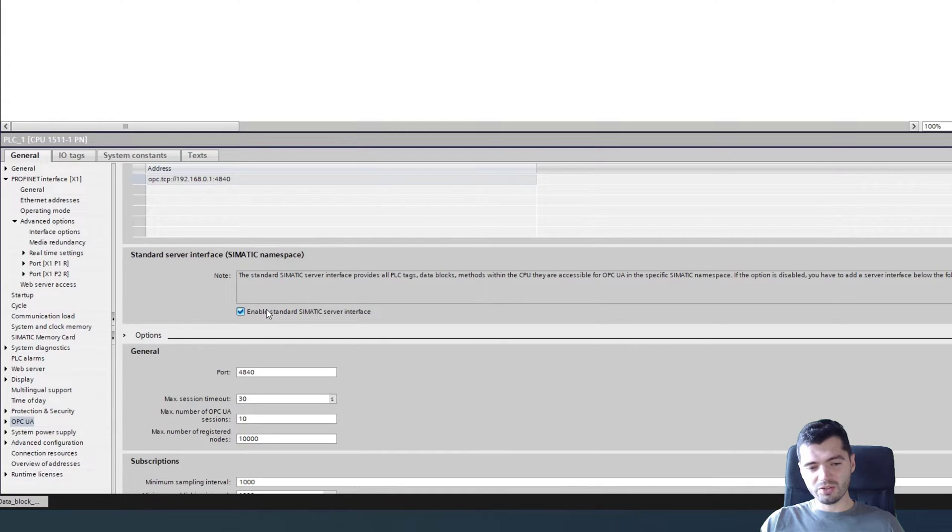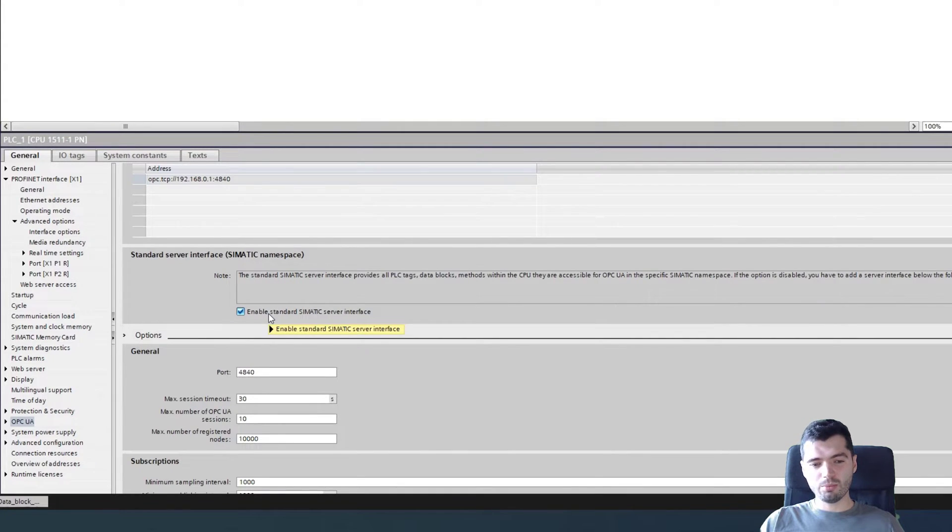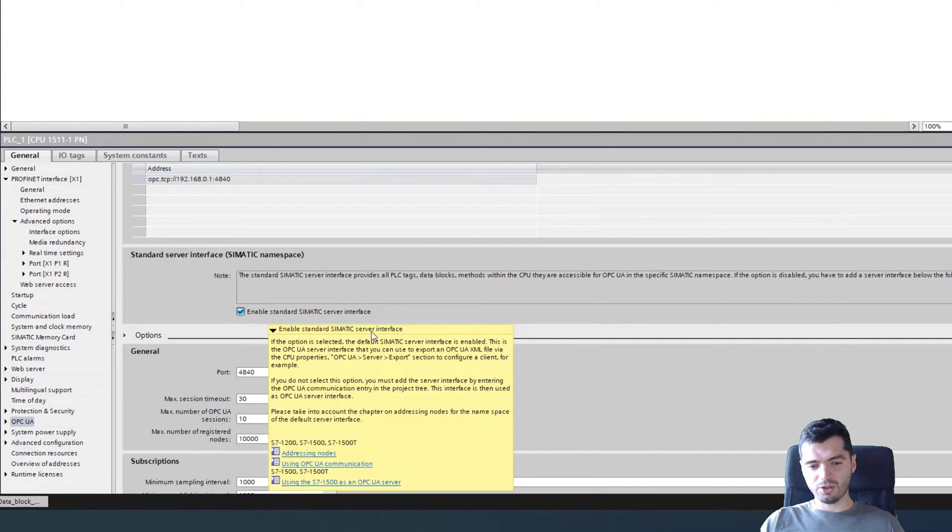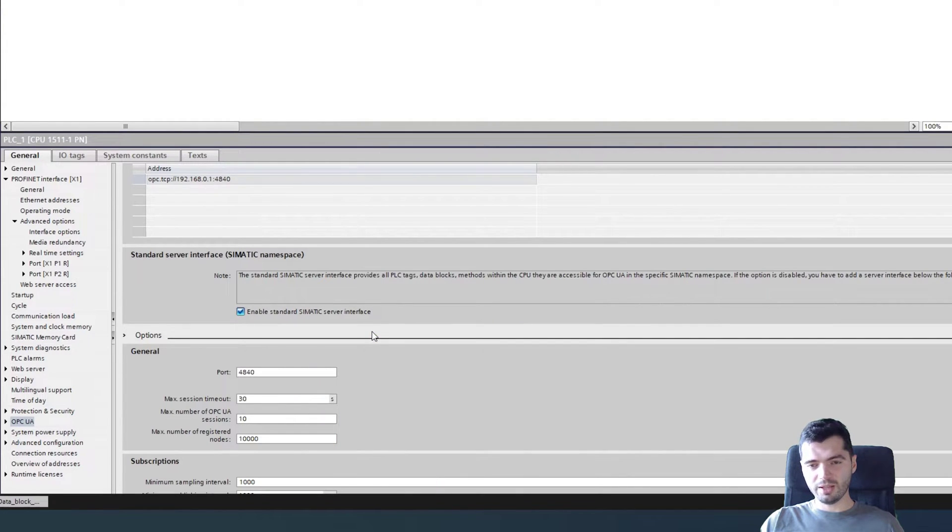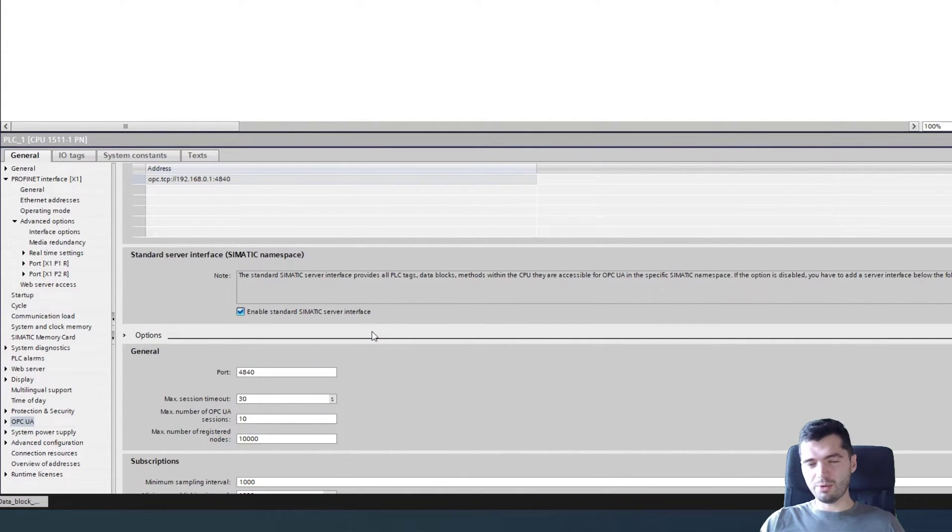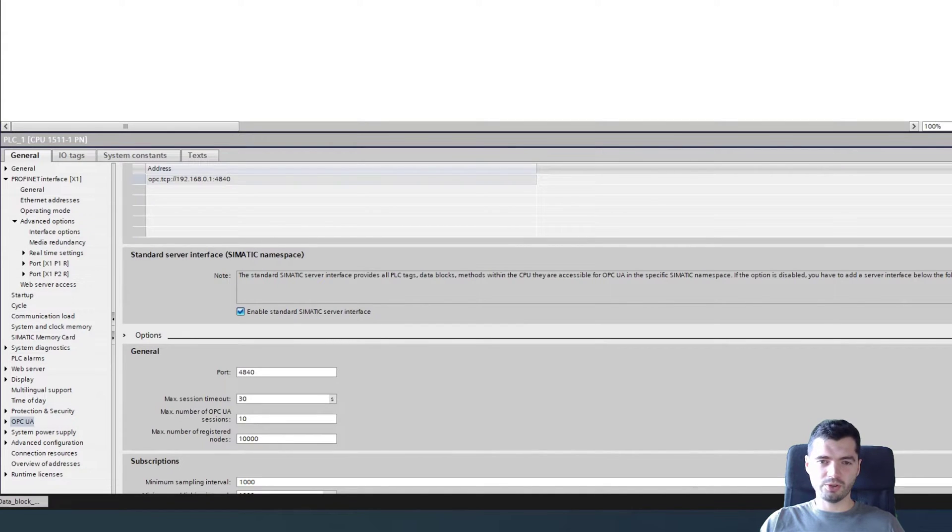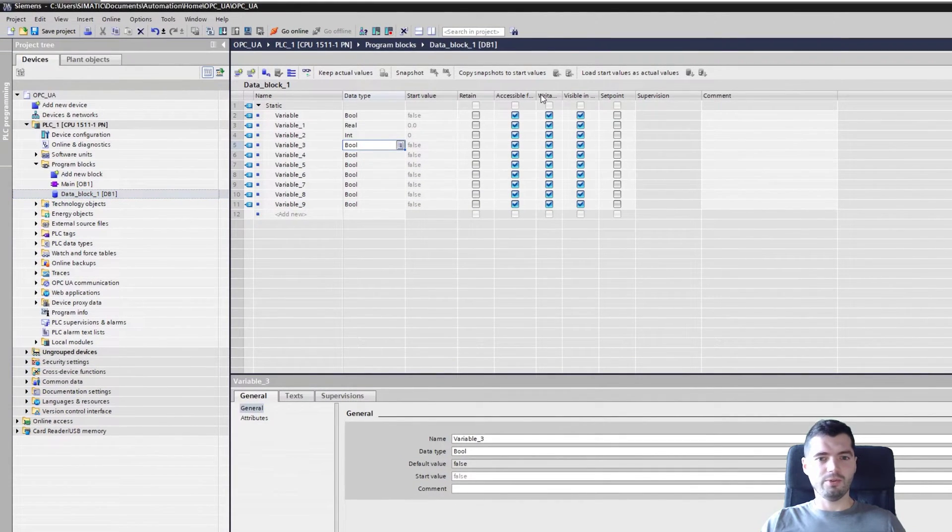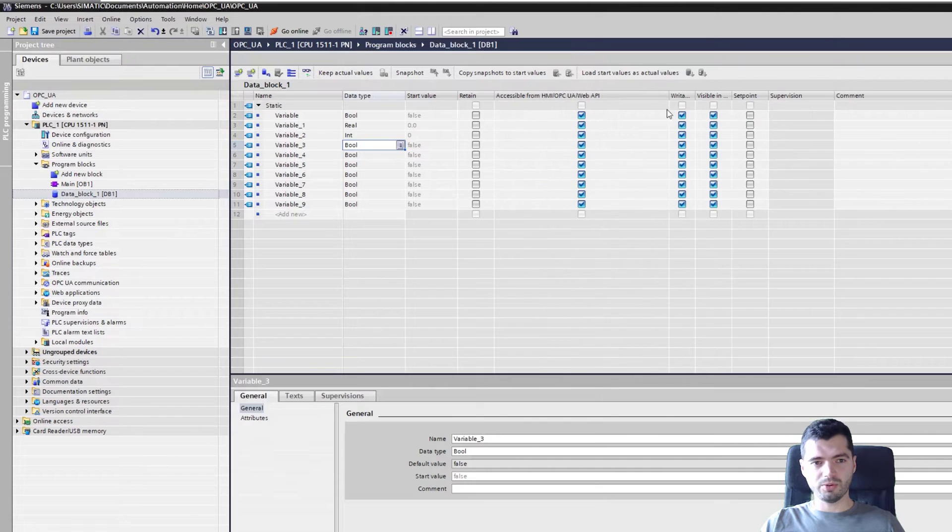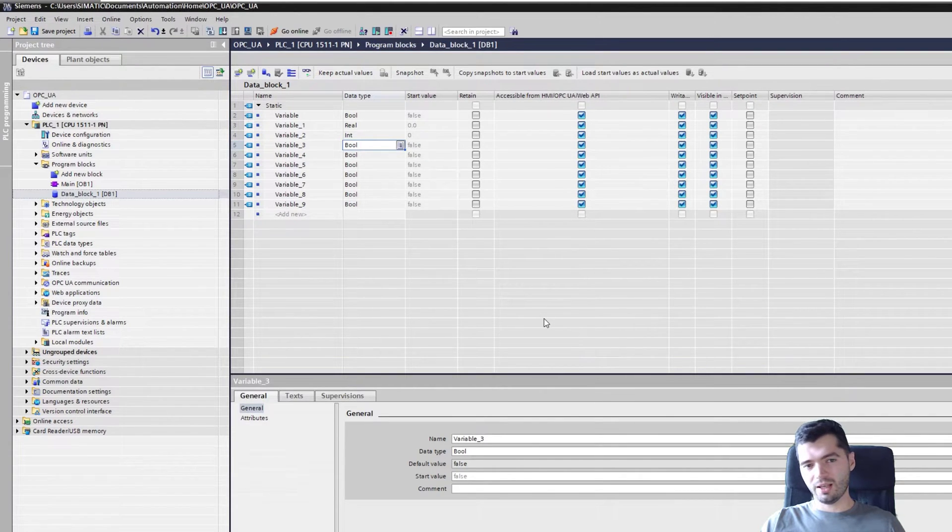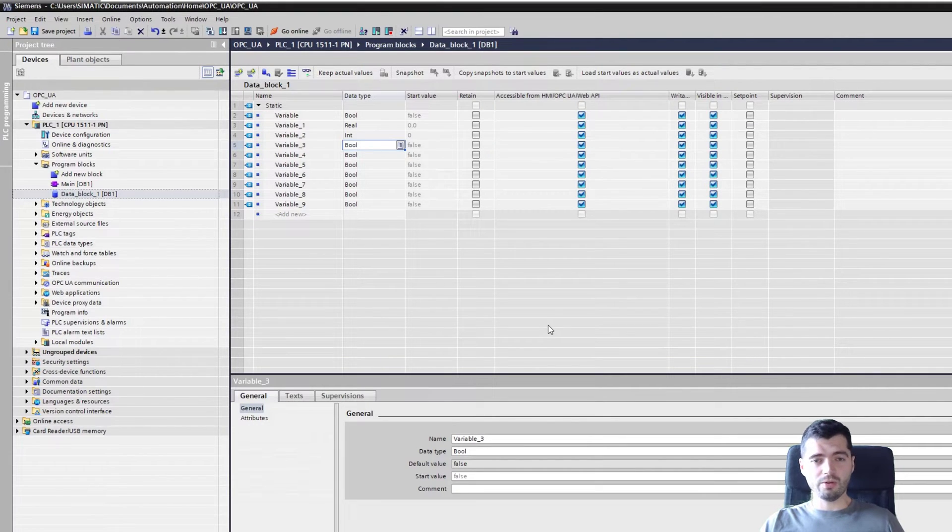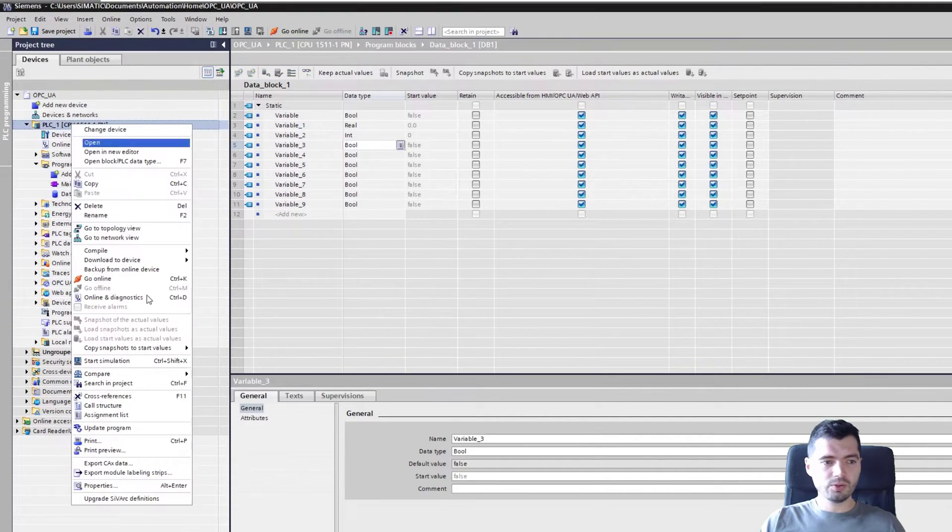Now this is the important setting. Enable standard SIMATIC server interface. What this setting means is if you tick this, it's going to create namespace three on your OPC UA server and basically expose everything to your OPC UA server. Everything that has a tick here will be exposed and available via an OPC UA server.